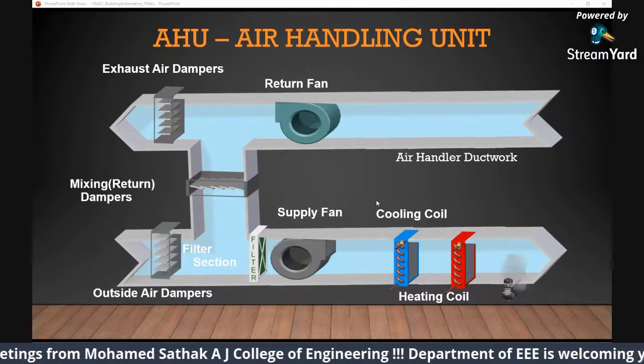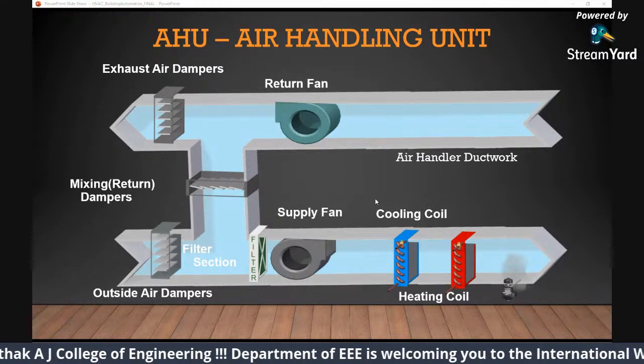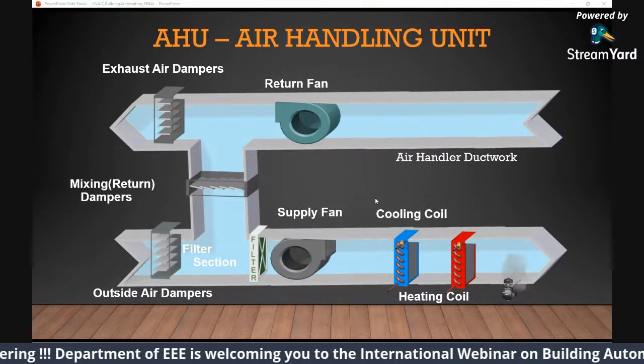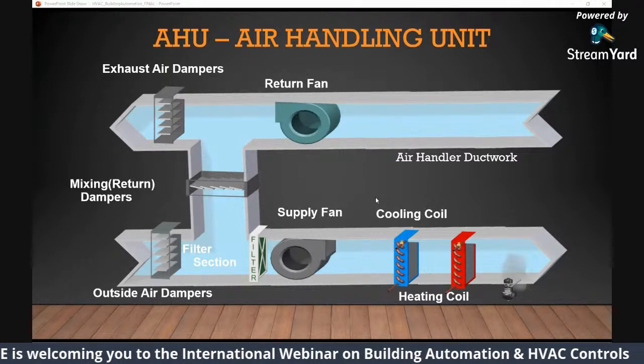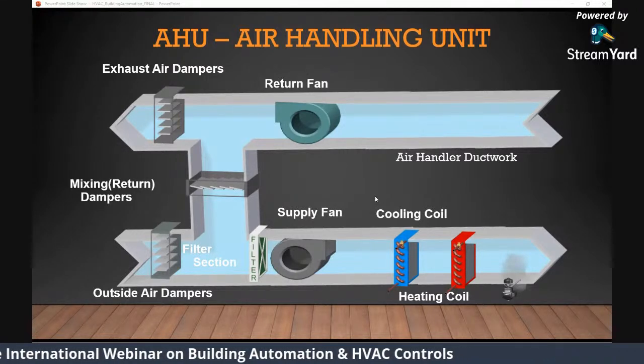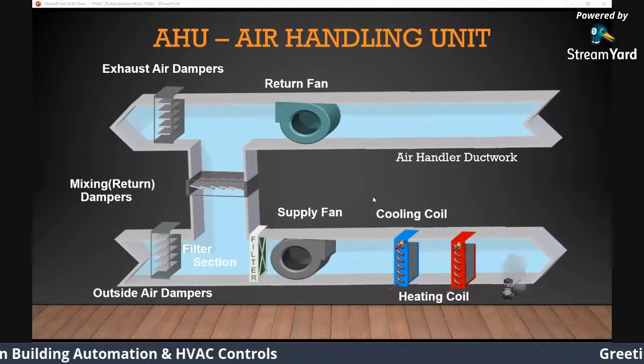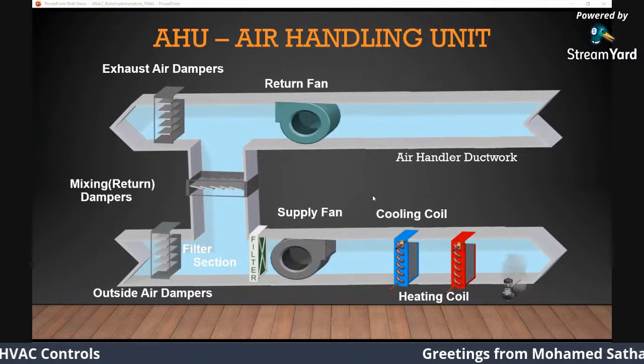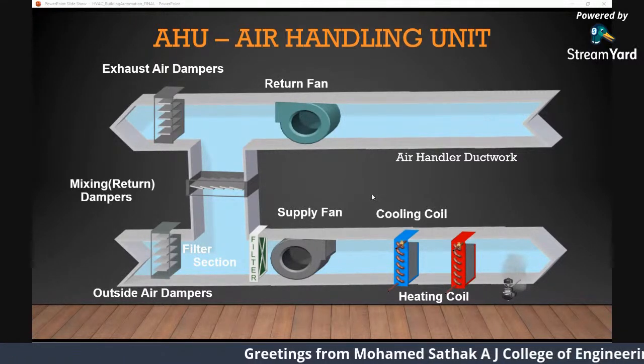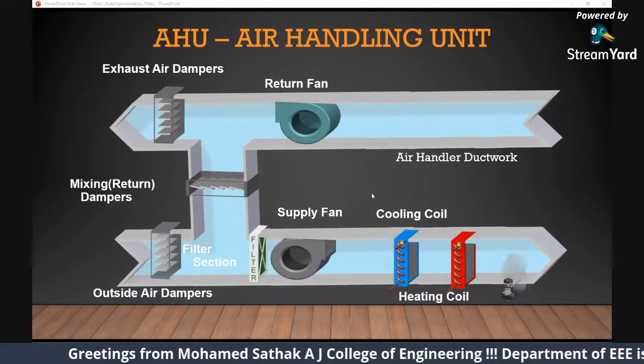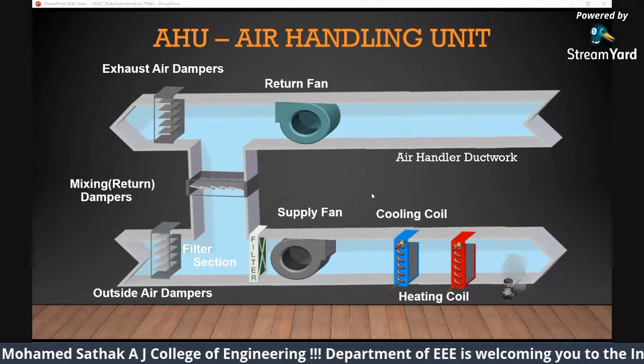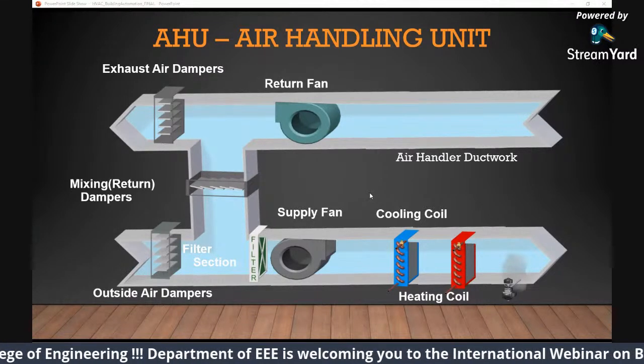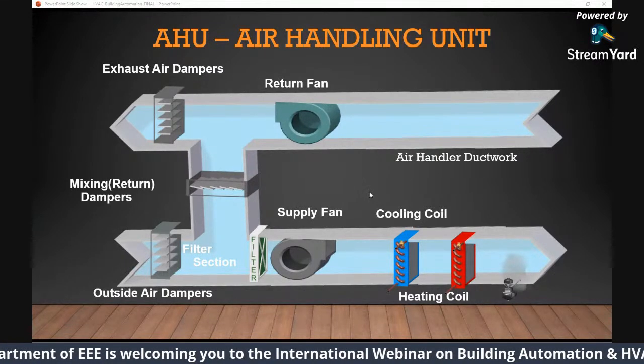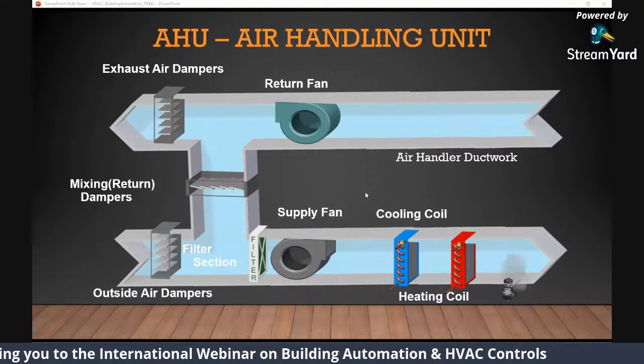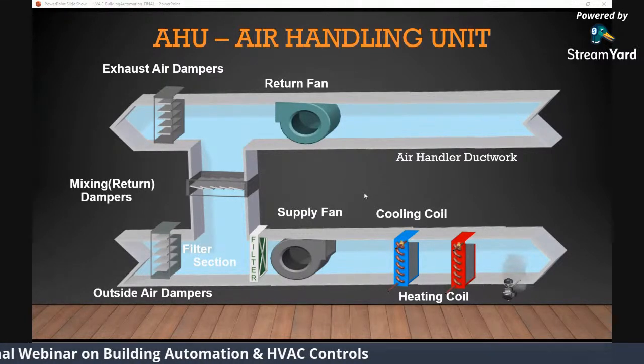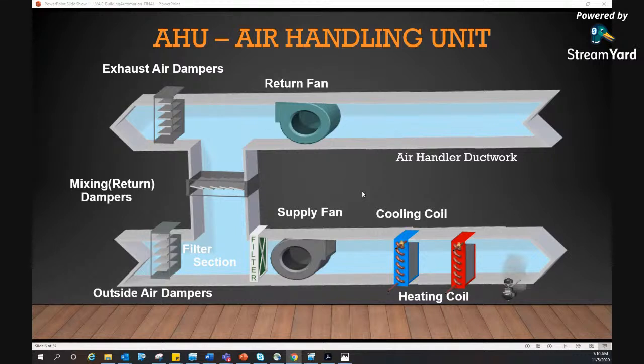Let's say there is Corona outside. During the Corona season, all the buildings will operate on outside air because they don't want to circulate the inside polluted air. Let's say it's a hospital. They will not circulate the air inside the building. They will open the outside air damper. Buildings like cinema theaters or a complex mall will circulate the air within the building, so they'll close the outside dampers. So dampers are an important component in an AHU. They act as a navigator whether to get the outside air or the return air. Again, you can compare them to windows in your house. If you want outside air, you'll open the window. If you want to circulate the air within your room, you'll close the window, right? So dampers are similar to your windows.